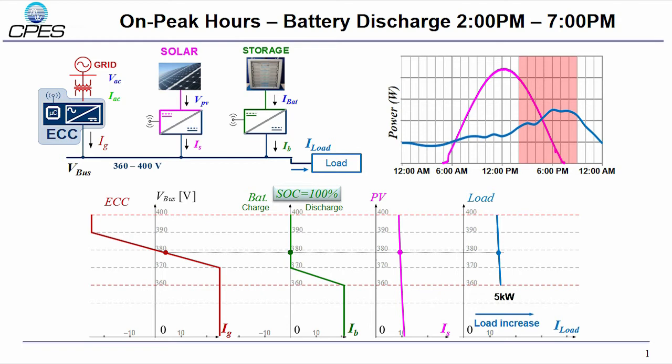Here we are showing an example of the on-peak hours for battery discharge during a day from 2pm to 7pm. The upper left shows the components who is involved in the current experiment. And the bottom showing the control functions of each component with the battery initial condition of 100% state of charge due to the noon solar charge. The first move of this experiment is the PV irradiation decrease. And due to the PV power decrease, more power will be supplied by ECC and the bus voltage drops.